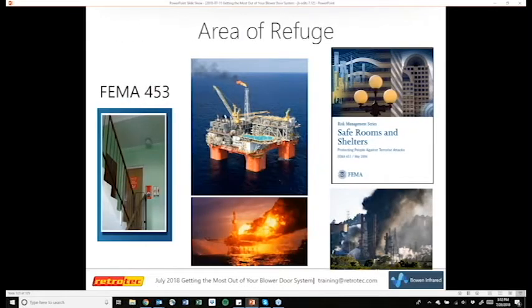Areas of refuge, such as safe rooms. Here's a picture of an oil rig, and then the bottom picture of an oil rig gone bad. So you have workers on there. It's in the middle of the ocean. They have nowhere to go, so you have to have some area of refuge, and it has to be airtight and secluded from any possible danger. And so using a blower door is to make sure that room is going to perform the way it's supposed to. And this is true for other industrial facilities as well.